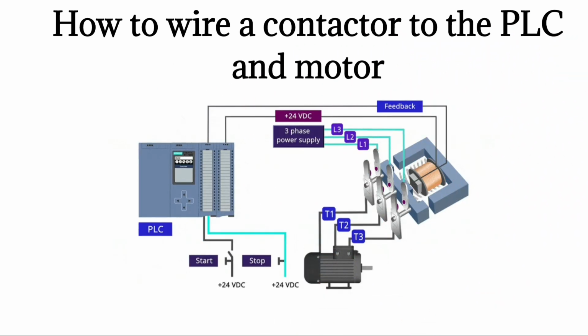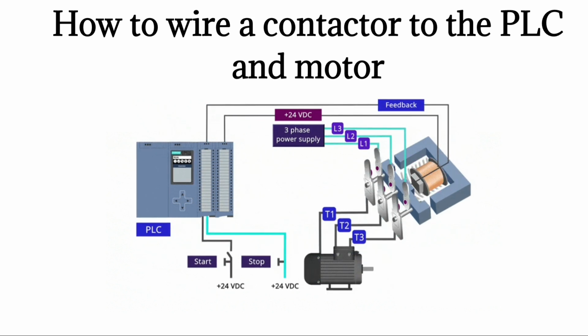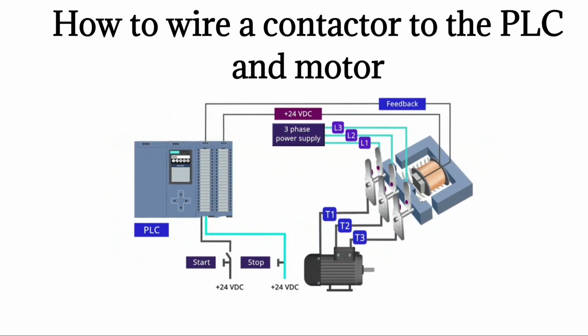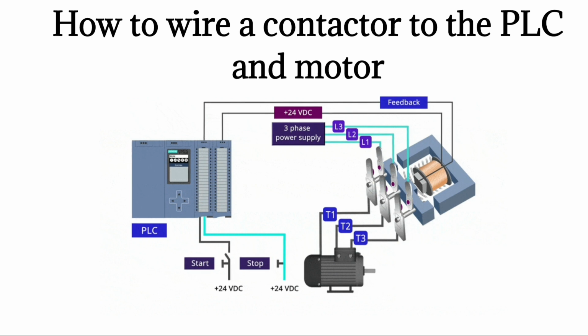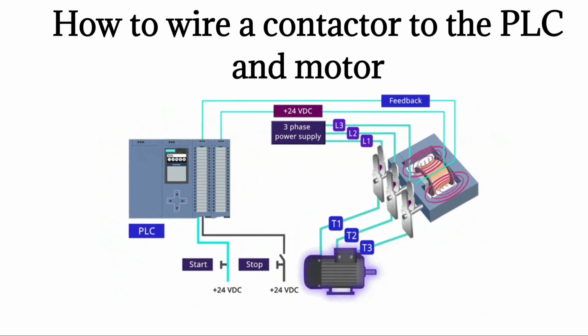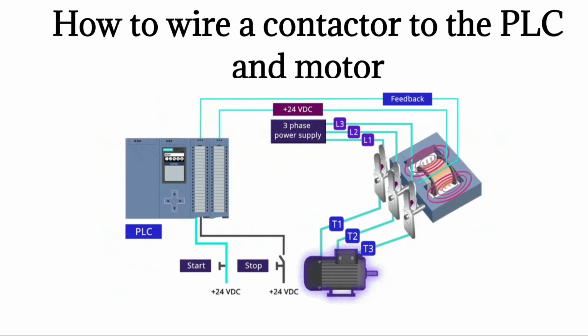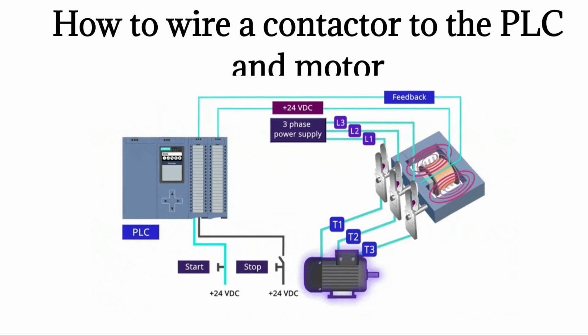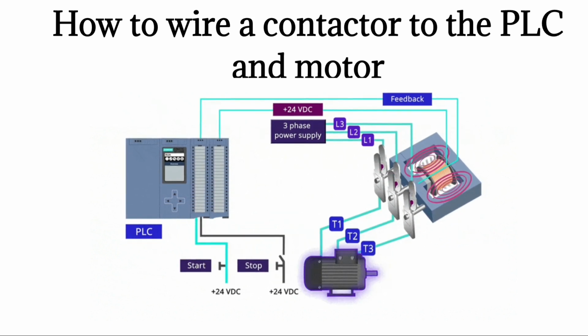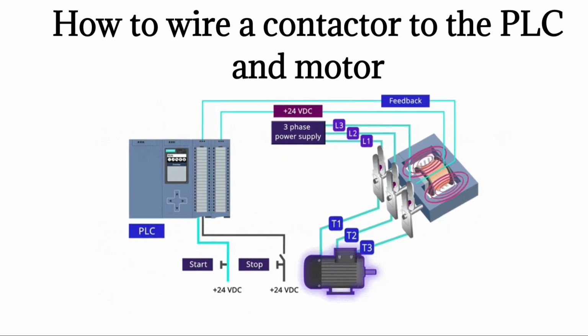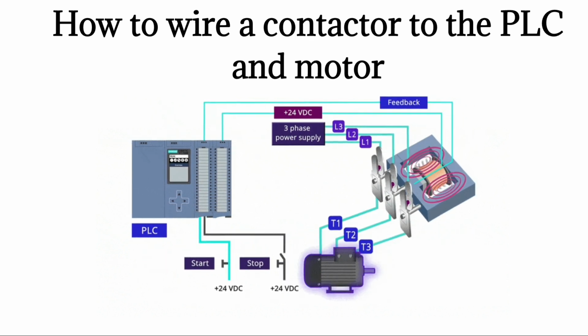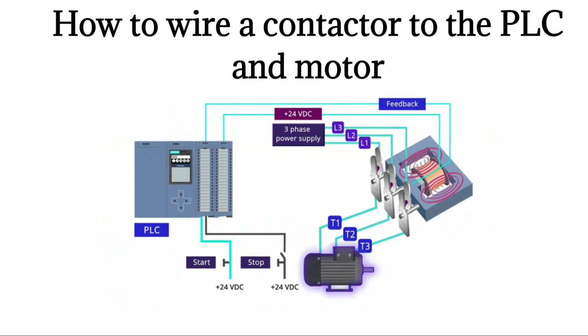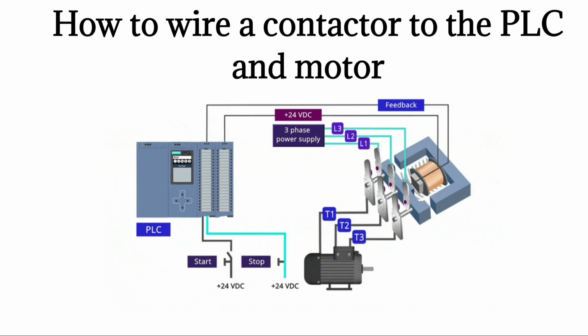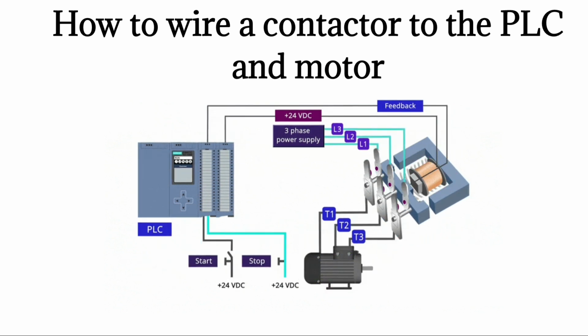How to wire a contactor to the PLC and motor. Okay, so, to control a motor using a PLC through a contactor, you need to connect the PLC output to the coil to be able to energize and de-energize it. You connect a three-phase power supply to L1, L2, and L3 from one end, and then from the other end, you connect T1, T2, and T3 to the motor. To be notified when the contactor is broken, you need to connect this auxiliary or feedback contact to the PLC input.